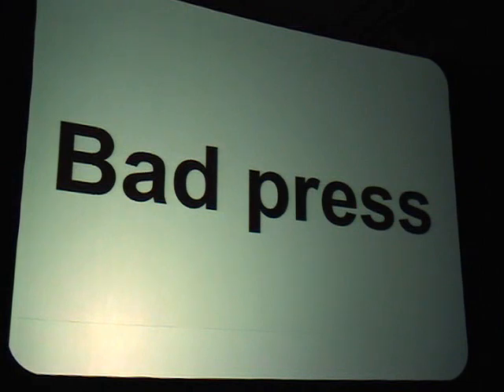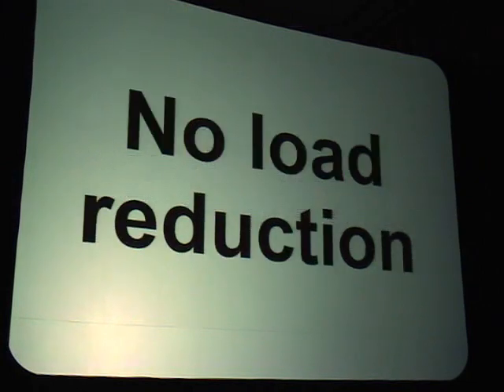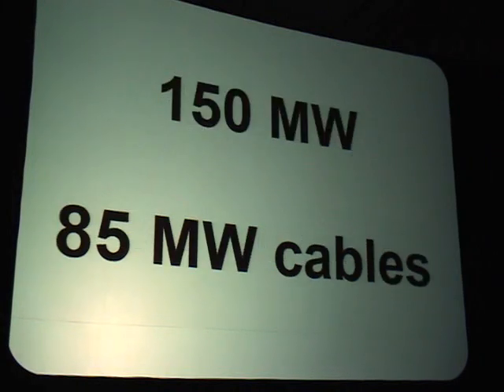So instead, they didn't tell anyone. There was no attempt to do load reduction whatsoever. So now they had a situation of 150 megawatts on 85 megawatts worth of cables. And a second cable failed.